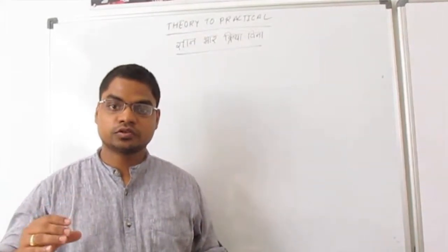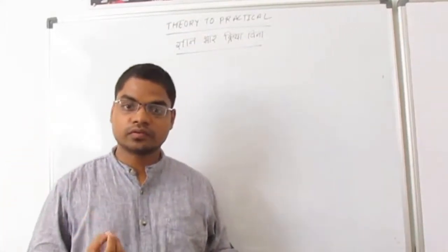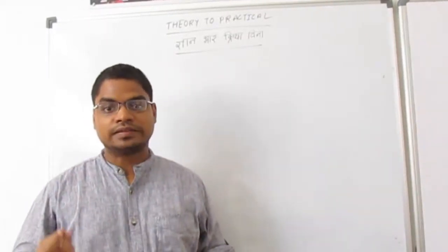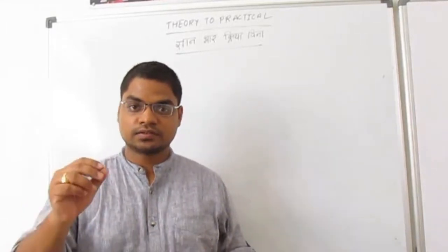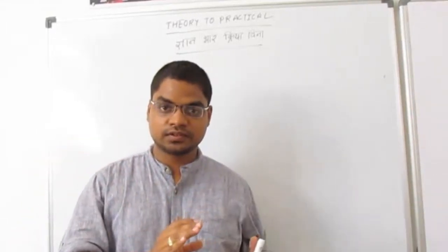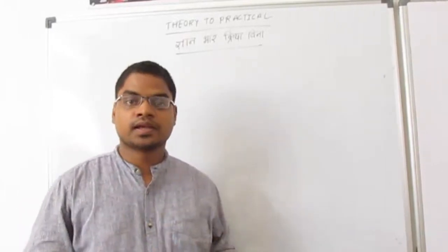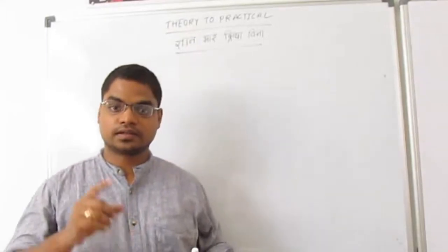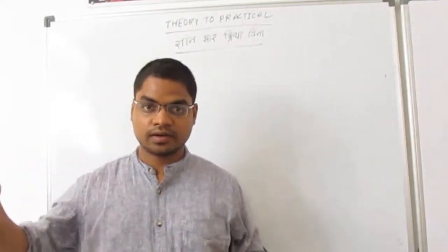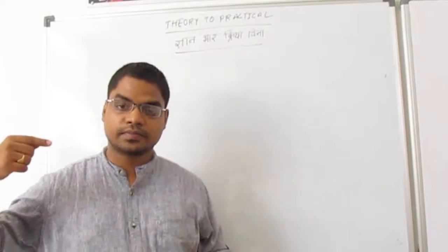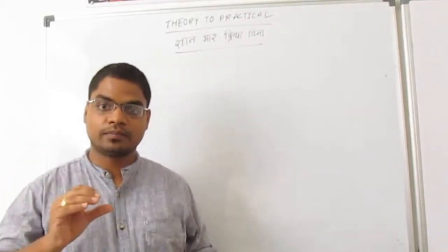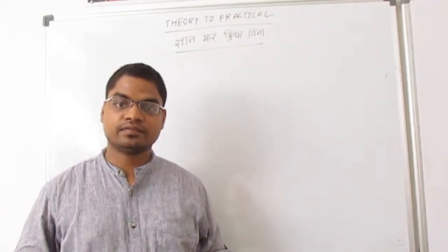So our aim is to lower the starting current. What we will do is use a simple star to delta converter. We will start the motor first with the star configuration, so the voltage will be less, and when the motor gets sufficient speed, we will use this star to delta converter, and now we will use the delta configuration and apply the full voltage. So by using the star delta converter, we have decreased the starting current of the motor.